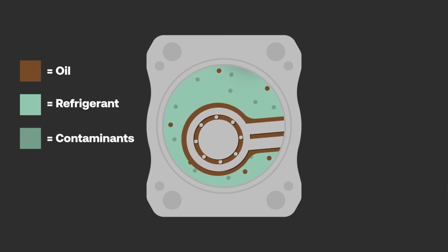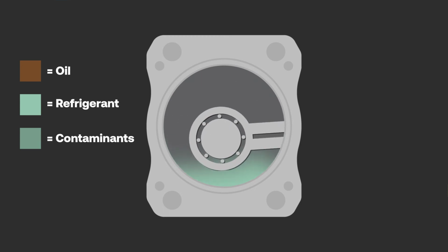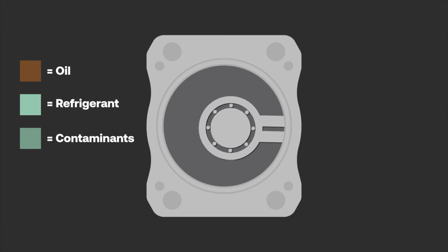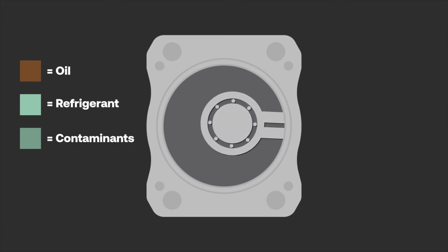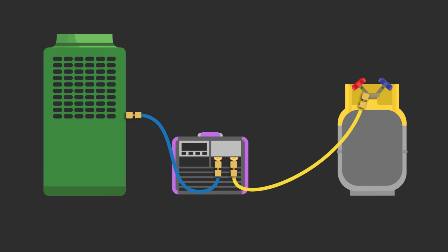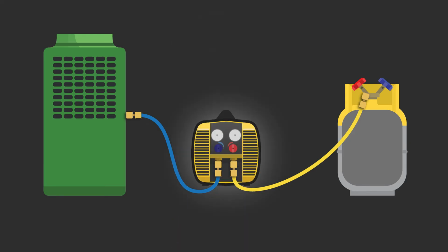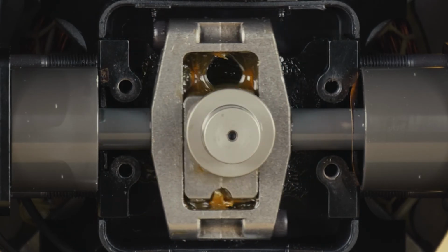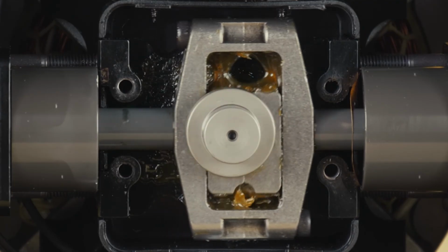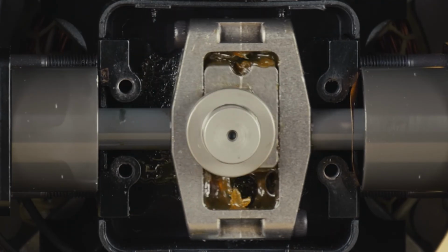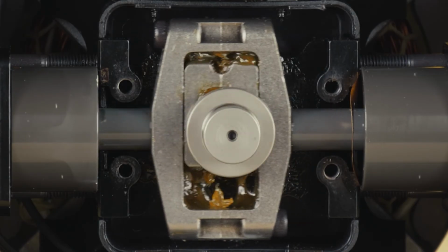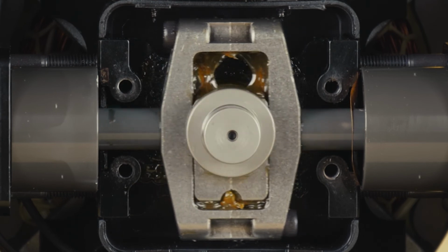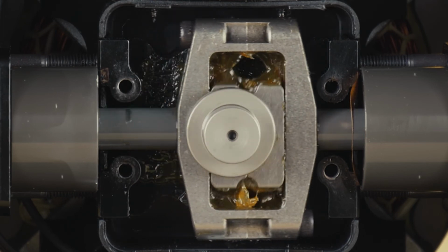Lastly, recovery machines of this design need a purge function to remove refrigerant trapped inside the flooded crankcase at the end of recovery. This adds an extra step to maintain EPA compliance and avoid cross-contamination. In order to have the fastest recovery times, you need a machine that can handle liquid refrigerants. Using a recovery machine with a permanently lubricated, refrigerant-isolated crankcase, like the G5 Twin, negates the risks associated with pumping liquid. Without the reliance on compressor oil, these recovery machines can pump liquid in virgin refrigerants without issue, allowing for a full-flow setup, increasing recovery speeds and utility on the job site.